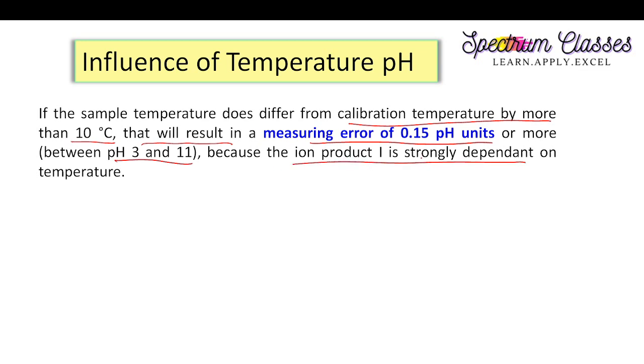The next point is the influence of temperature on pH. If the sample temperature differs from the calibration temperature — for example, if you calibrated your pH meter at 25°C and the sample is at 35°C — there is a temperature coefficient. For a 10°C difference, there will be an error of 0.15 pH units, because the ionic product Kw = [H⁺][OH⁻] strongly depends on temperature.